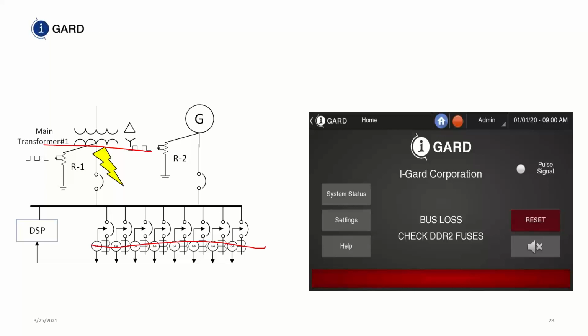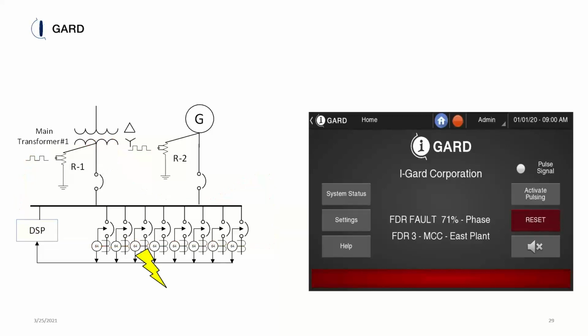So we tell you where to start looking for the fault, even though the fault is on the line side or inside the generator or inside the transformer. We tell you there is a fault, it's on the line side, it is considered a bus fault. The transformer secondary and the generator are still protected by the same high resistance grounded system. There's a fault on feeder number 3. We say that there's a fault on feeder number 3.